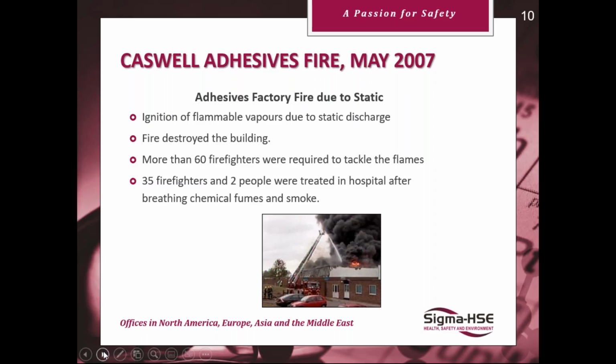One of the problems when working with adhesives is that a lot of them are insulating. They often cover the floors and the equipment, and it results in isolated people and equipment. And this can often result in a static discharge. I'm not sure what happened in this one, but I would assume from experience that this is probably the cause of it.